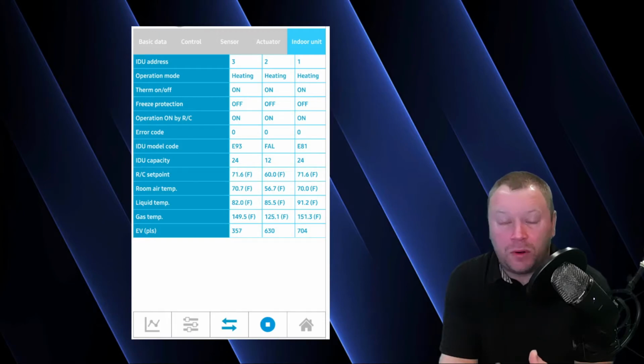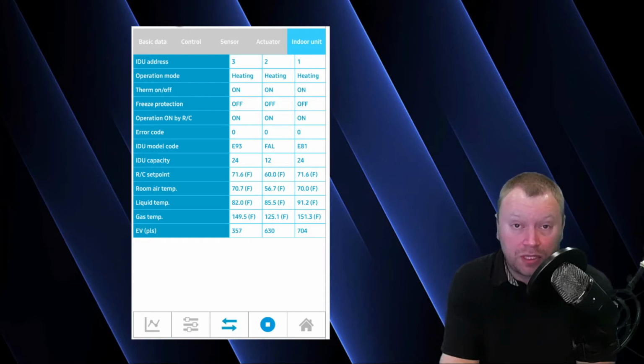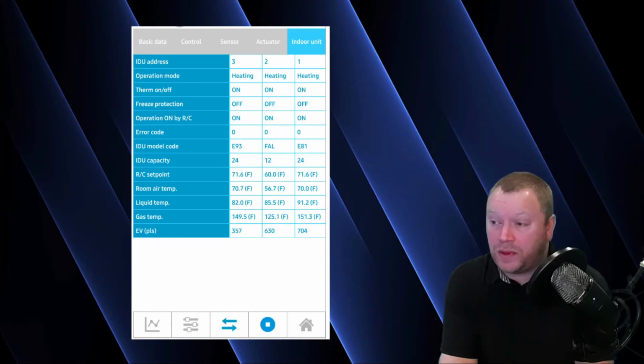Now, I'm only 9 to 10 minutes into the heat cycle here while I'm recording data. If I was to wait another 10 minutes, those gas temperatures are going to continue to climb. But what we're going to look at each indoor unit is 2 things. We're going to look at the liquid temperature to calculate the amount of subcooling which is occurring at each indoor unit independently. And we're also going to look at the electronic expansion valve position. So first, let's start with the liquid temperature. So the liquid temperature on each of these units, 82, 85, and 91 degrees respectively.